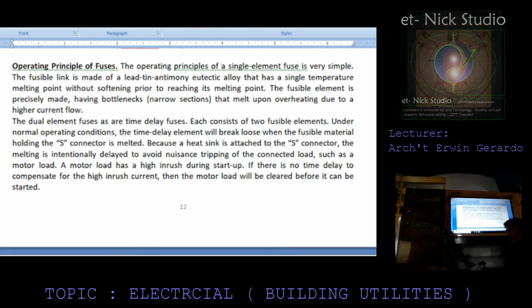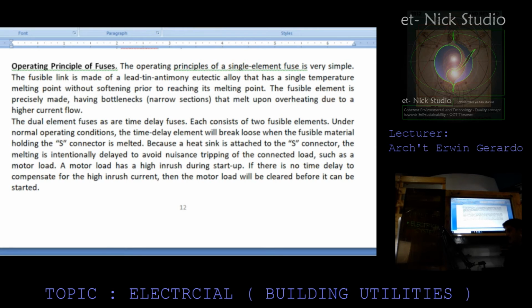The dual element fuses, also known as time delay fuses, each consist of two fusible elements under normal operating conditions. The time delay element will break loose when the fusible material holding the S connector is melted. Because a heat sink is attached to the S connector, the melting is intentionally delayed to avoid nuisance tripping of the connected load, such as a motor load. A motor load has a high inrush during startup. If there is no time delay to compensate for the high inrush current, then the motor load will be cleared before it can be started.